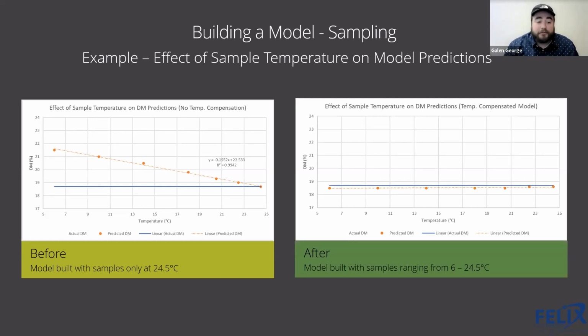That model was then used to try to predict fruit that were at 6, 10, 14, 18, 20, it looks like 20.5. So a whole range of sample temperatures. And as you can see, there is a huge bias in prediction that gets smaller and smaller as we approach the actual calibration data set temperature, which is 24.5. Now, if we use a model that is built with samples that range from 6 to 24.5, and then use that model to predict samples within that same temperature range, the predictions all have a consistent bias, and they're all very close to the actual dry matter value. So as you can see, temperature does have a significant impact, and it's not a constant impact. That is why it is important to include temperature as a variable when you are building out your sample plan.